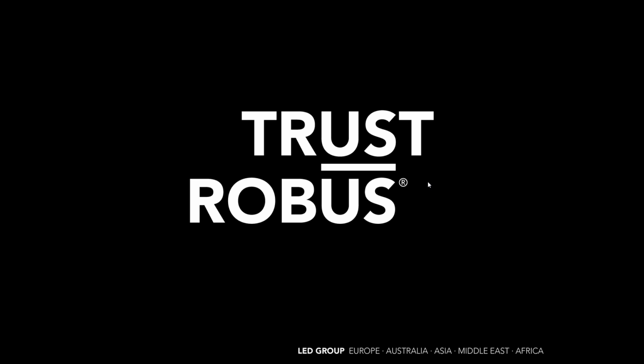It's not that it's been found that it's been way out and over-predicted the lifetimes from this process. They're pretty accurate, and to be honest, I think they're a little bit conservative, and certainly manufacturers like ourselves and lots of manufacturers do this: although the life that is calculated might well be, say, 60,000 hours, we always tend to pull it back a little bit and we'll quote maybe 50,000 hours for that particular product.